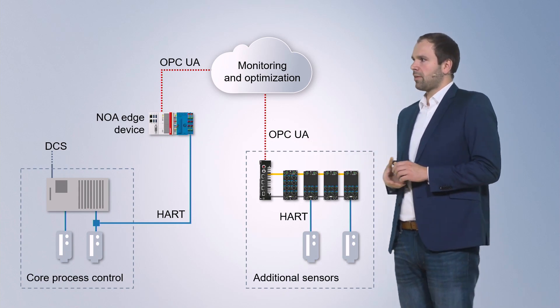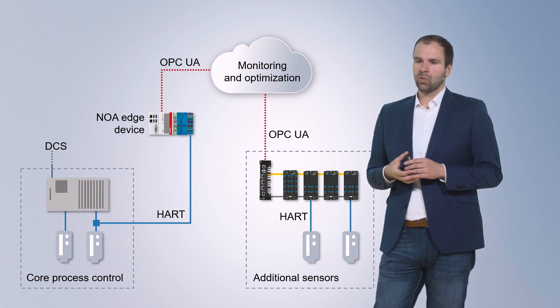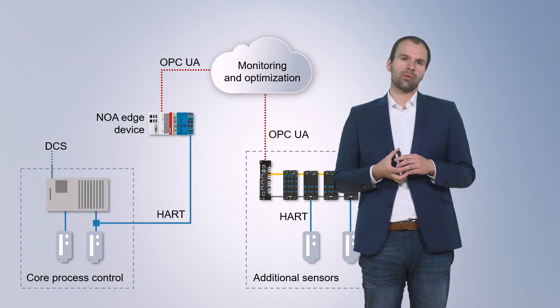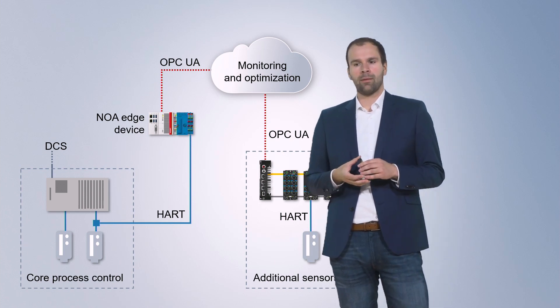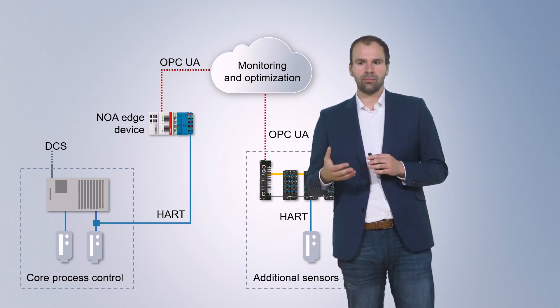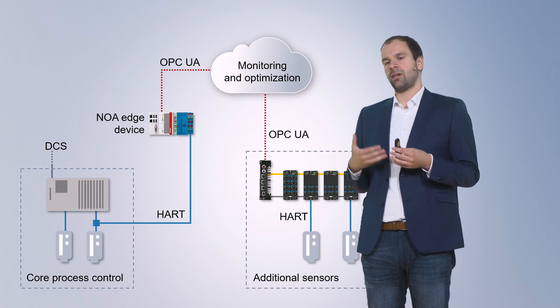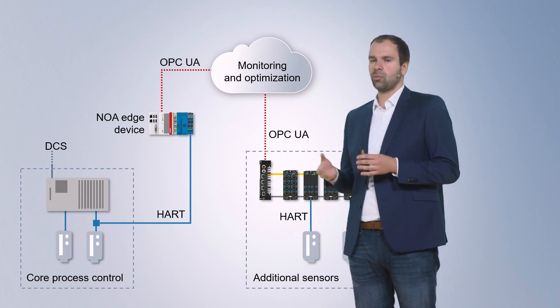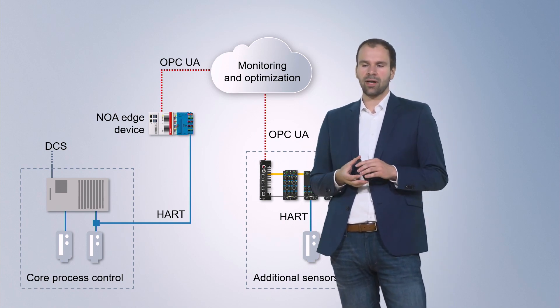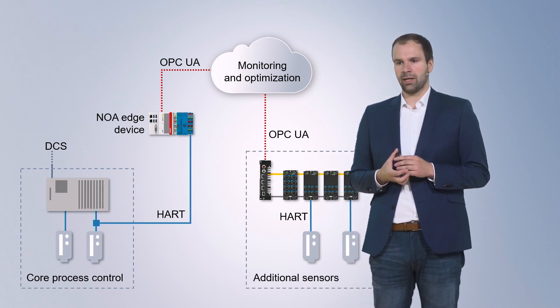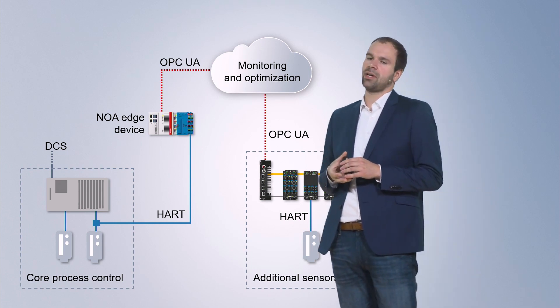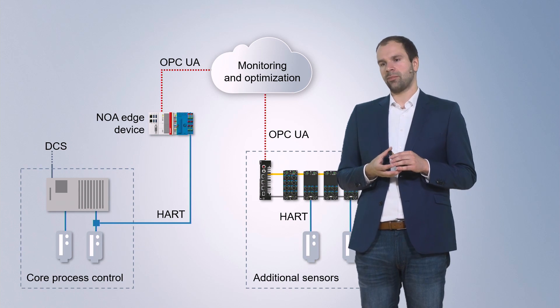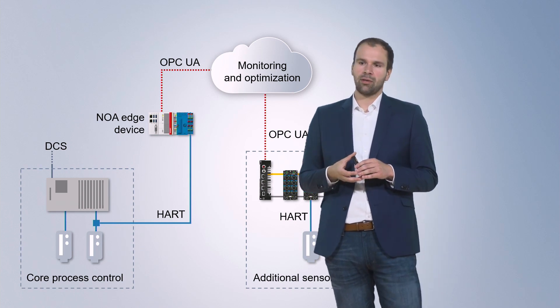Looking at the devices in the system, the existing DCS system connects to the field devices. The vast majority of process instrumentation uses the HART protocol. Often, only the 4 to 20 milliamp signal is read by the DCS system, and all additional information inside those smart devices is lost. With the Edge device, we can connect to the HART interface and read all further information. The Edge device establishes the HART communication, reads the data, converts it if necessary, and maps it to the NOA information model so the data becomes available through the OPC UA server.